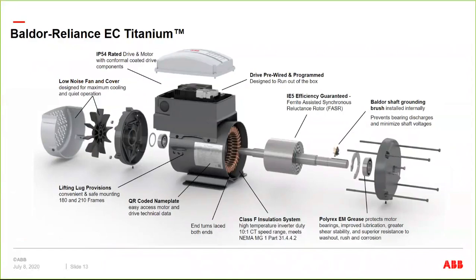Because these are all run on a drive, you will have instances, depending on the grounding system, of common mode noise and voltages on the shaft, which can lead to bearing damages. So we want to eliminate that concern and make sure you don't have to worry about it. So all of the product, including the motor only that is sold for a separate drive, comes with an internal shaft grounding brush. Now we can do options like an Aegis ring or ceramic bearings, but the stock product has the ground brush in it.